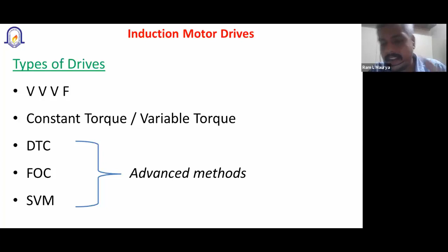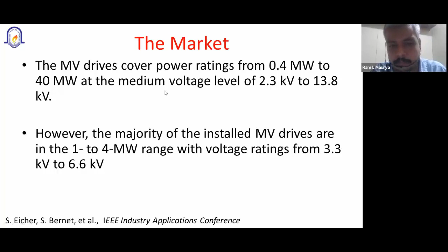So for the market, I will just talk about the MV market, that means the medium voltage market. The medium voltage market is approximately from 2.3 kilovolt to 13.8 kilovolt, and drives of 0.4 megawatts to 40 megawatts. But currently, as you can see, only 1 to 4 megawatts is being used, and the voltage range being used is 3.3 to 6.6 kilovolt. This is the market survey done by ABB.